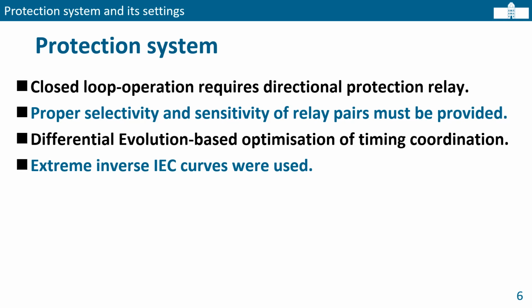If we are talking about the protection system, closed-loop operation requires directional protection relays. Proper selectivity and sensitivity of relay pairs must be provided. To do this, differential evolution-based optimization of timing coordination is performed, and in this case we use extremely inverse IEC curves.